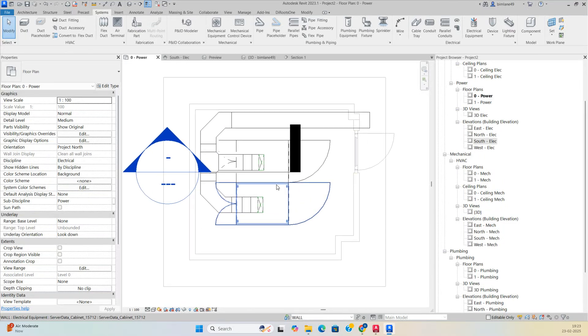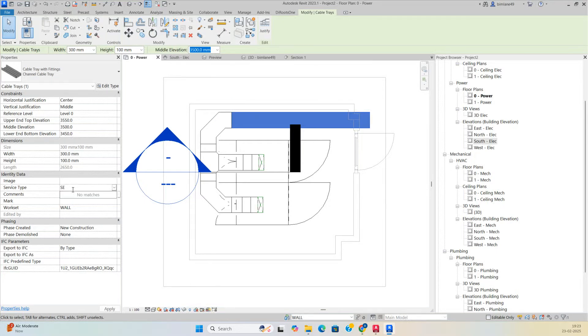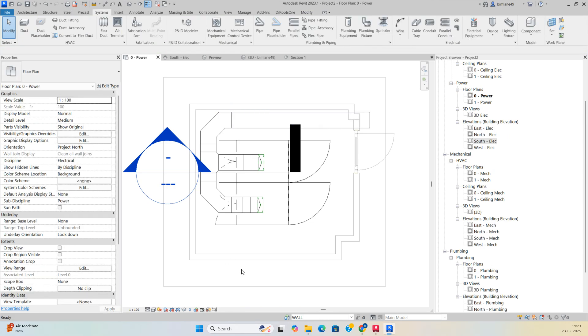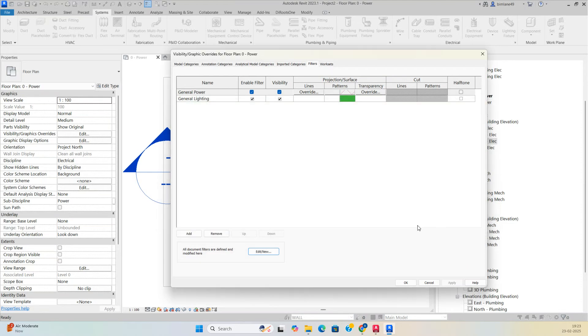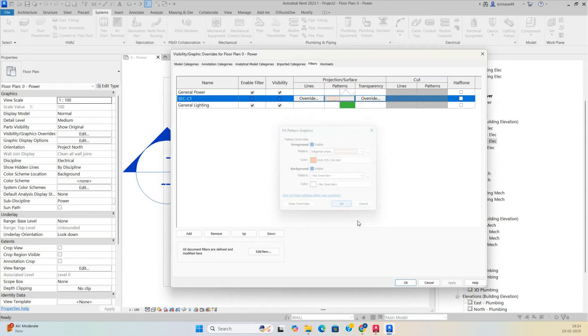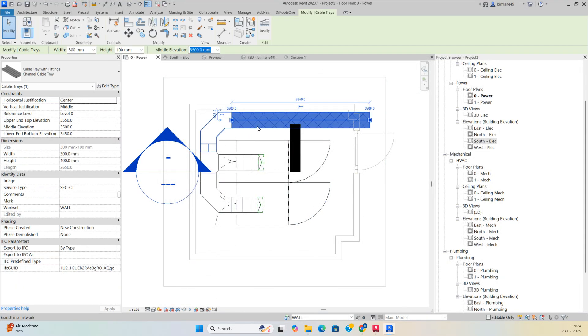To apply color filters, type VV, go to Filters, and create a new filter named 'Security CT'. Select category Cable Tray and Cable Tray Fittings, set the rule to Service Type equals 'Security CT'. Add the filter, assign a pattern and color for the security cable tray, then click Apply.